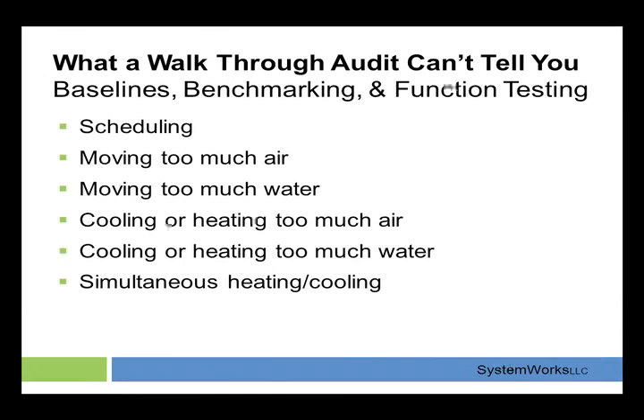Scott referred to cooling and heating. If the unit in the wintertime is cooling the air down to 55 degrees, and then we're warming it back up for the classroom, that's wasteful. So we should be resetting that discharge air temperature at the main air handler up warmer and warmer as it gets colder outside, so that we don't waste a lot of energy reheating that air.